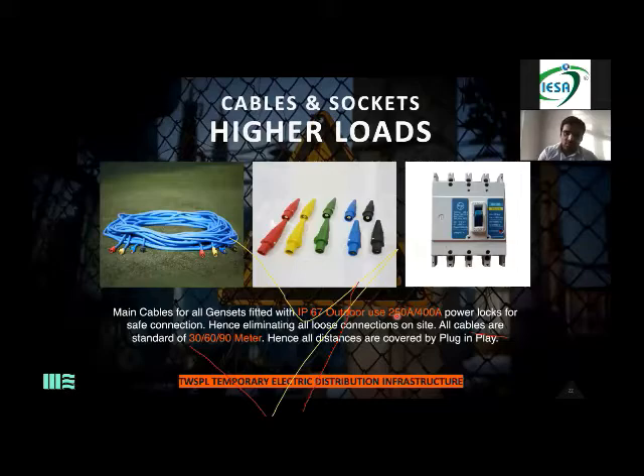Now the loads have become higher. So I've given you a calculation: if somebody has asked you for 150 kilowatts, you multiply it by 1.7, and you will get roughly around 250. So you use the right cable as per the size, and the right power lock. These power locks are all male and female. So if you have to travel a distance of 100 meters or 50 meters or 200 meters, we are only doing plug and play.